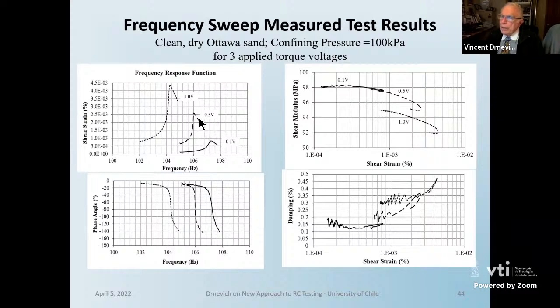And the corresponding phase relationship looks like this. Now, if we then up the power to the coils and do the same thing, we will find that the curve becomes higher. You apply more force, you're going to get a larger strain. You can see that the value of the shear modulus, or the resonant frequency, reduces. At low input power, we had a resonant frequency of about 107.5. Here we're down to 106. And we have a curve that's getting steeper in shape. And finally, if we apply an even larger torque to the specimen, we can see that the resonant frequency comes lower. But we have data for all of these points here, and we have both the magnitude and the phase.